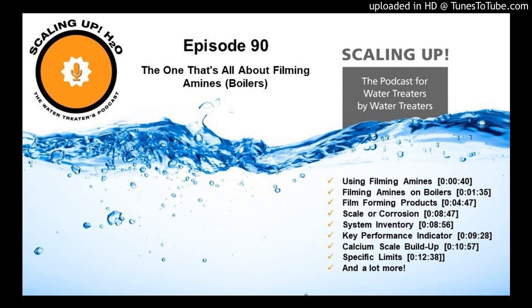I was so upset. That boiler, it went from red to black. I mean, it was just horrible. And then in about 3 days' time, it went crystal clear. We did exactly what you said. We were blowing down. And today, that's probably been 8 years, that boiler looks pristine. Yeah, which is what we see.